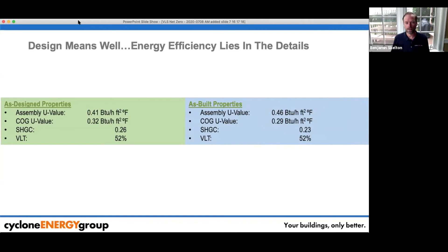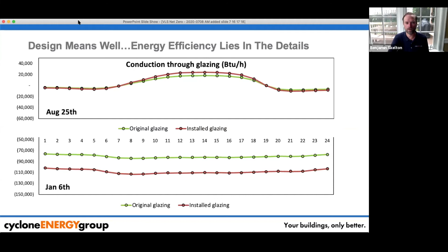In summer it's not as big a deal since there isn't a large temperature difference between inside and outside, so conduction isn't as significant. If we're maintaining the store at 77 degrees Fahrenheit with it around 92 to 95 degrees outside—this August 25th date was likely a peak day, about 95 degrees—you see roughly a 4% increase in energy, which is still notable. Looking at January 6th, a polar vortex day around minus 10 to 12 degrees—again a design condition, as Alan pointed out earlier—you can see we're consistently pouring a tremendous amount of energy, measured here in BTUs. This represents about a 15% increase in energy.